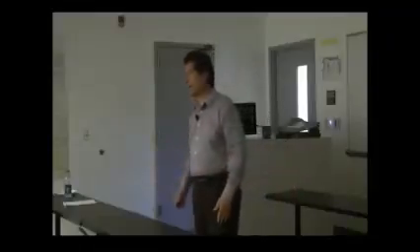But on these particular sections, there are different levels of voltages. You could have 208, 480. But every one of these is going to have a light bulb, believe it or not. Red for off, green for on. Do the light bulbs burn out? So when it's on, and you know it's on, and there's no green light bulb, that's a clue. So part of the maintenance program is first going through all the ones that are energized. There's a green light bulb letting me know it's an energized circuit. If it's off, I'm going to have a red light. So again, part of the routine maintenance requirements.